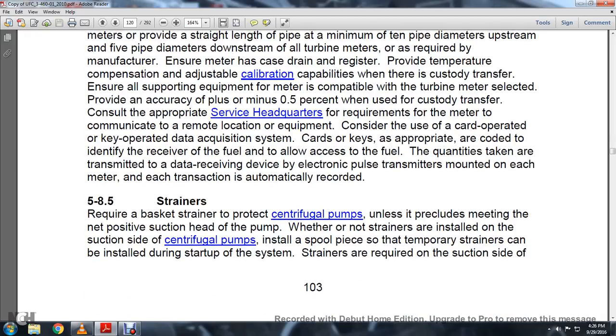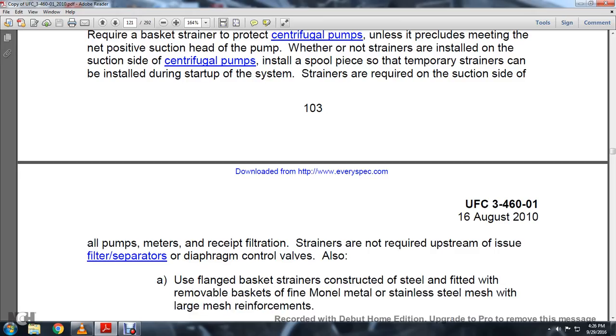5.8.5 Require a basket strainer to protect the centrifugal pumps unless it precludes meeting the net positive suction head of the pump. Whether or not strainers are installed on the suction side of the centrifugal pumps, install a spool piece so temporary strainers can be installed during startup of the system. Strainers are required at the suction side of all pumps and meters. Receipt filtration strainers are not required upstream of the issue filter.